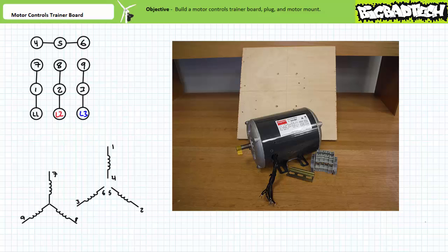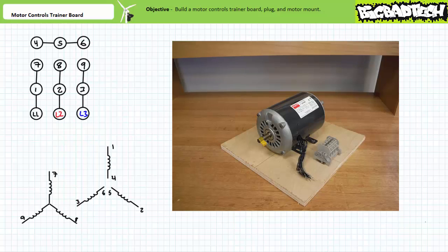We're going to use a quarter horsepower, dual voltage, 9-lead Y-configured motor for later applications exercises. This motor will always be used in the low voltage configuration. However, we still might need to disconnect it from our motor control circuit for transport or troubleshooting scenarios. So we'll mount the motor to another board as well as another set of terminal blocks affixed to a short length of DIN rail. The motor can now be placed in the low voltage configuration using the relatively secure terminal blocks instead of some chintzy wire nuts.